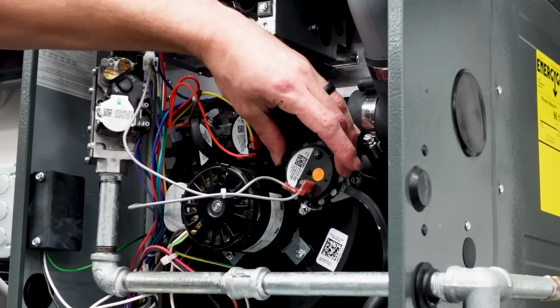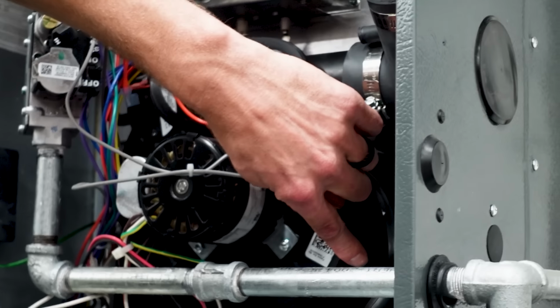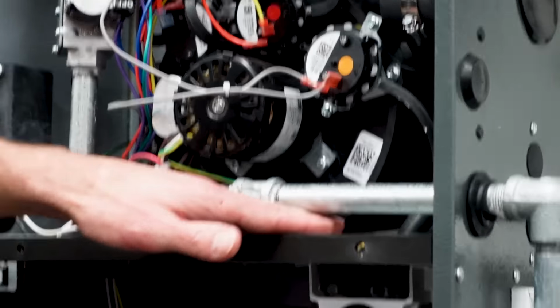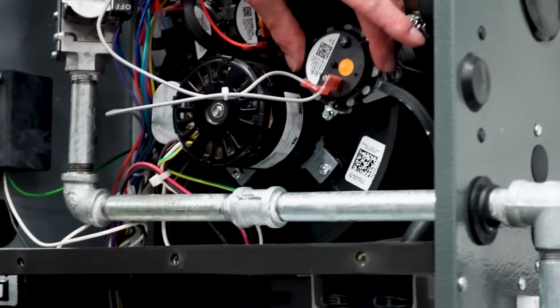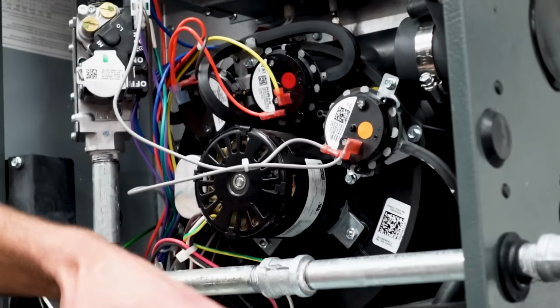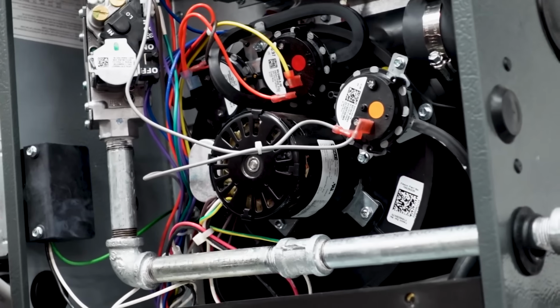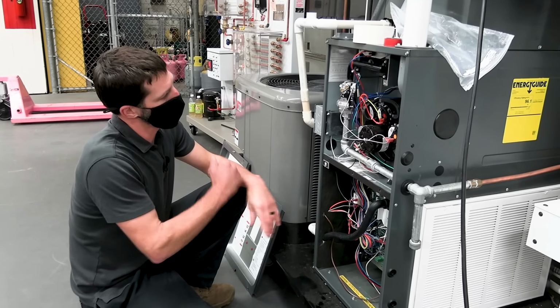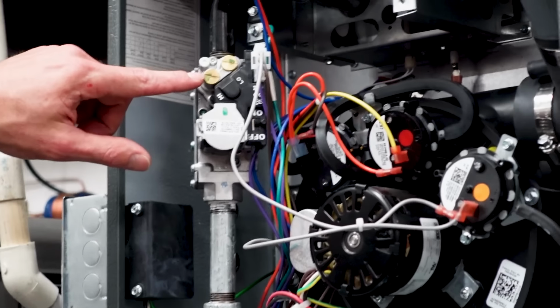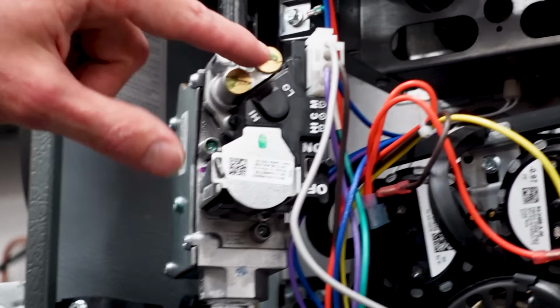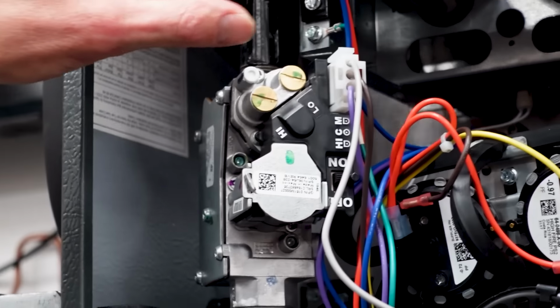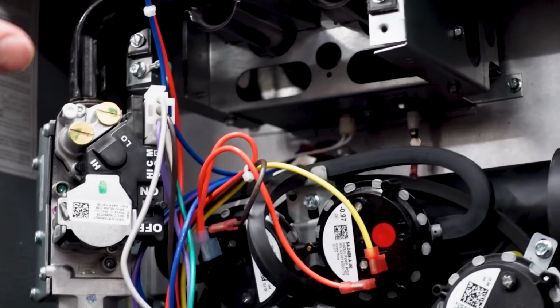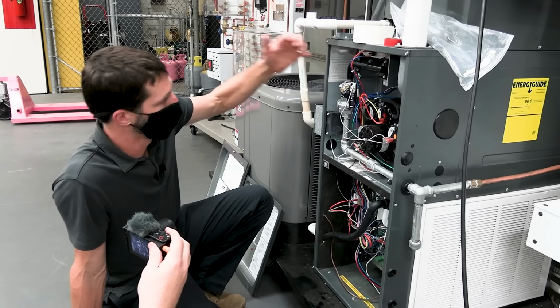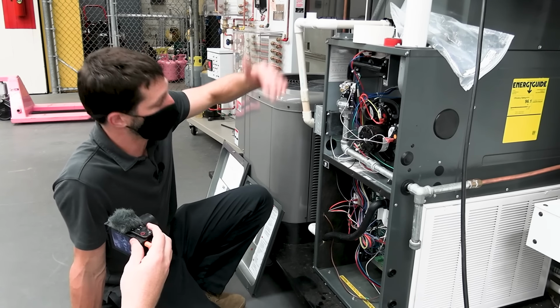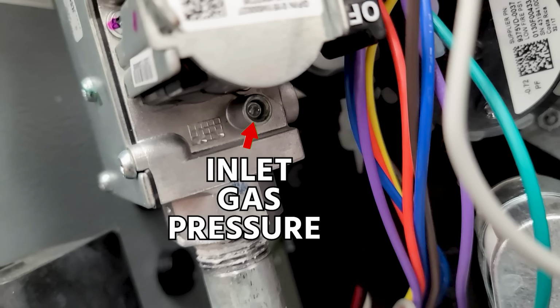And I know I covered this already, but this tube goes down to this lower part where the condensate is, and so that's how you can tell that is the one as a safety device to make sure that the condensate does not overflow. So if you are going to adjust the gas pressure, you're going to take these screws off right here and here. If it was a sealed combustion, you'd want to take that door off as well, so you had the pressure that's in the room. Looks like that's going to be where your inlet gas pressure is going to be taken at.